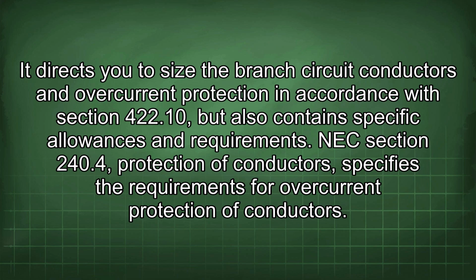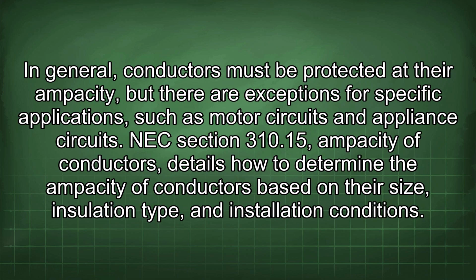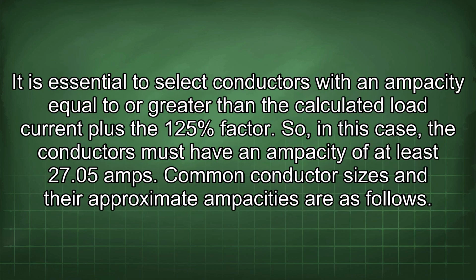specific allowances and requirements. NEC Section 240.4, Protection of Conductors, specifies the requirements for overcurrent protection of conductors. In general, conductors must be protected at their ampacity, but there are exceptions for specific applications, such as motor circuits and appliance circuits. NEC Section 310.15, Ampacity of Conductors, details how to determine the ampacity of conductors based on their size, insulation type, and installation conditions. It is essential to select conductors with an ampacity equal to or greater than the calculated load current plus the 125% factor. So, in this case, the conductors must have an ampacity of at least 27.05 amps.